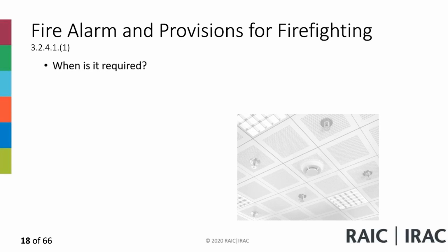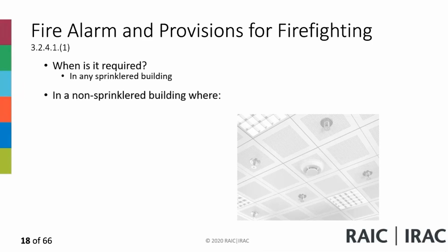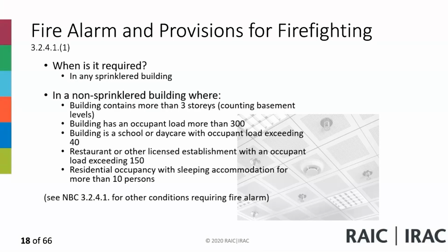When is a fire alarm required? Keep this code, 3.2.4.1. So every time I have a sprinklered building, I must have a fire alarm system. And then in other buildings, whether sprinklered or not, you need to take a look at 3.2.4.1.